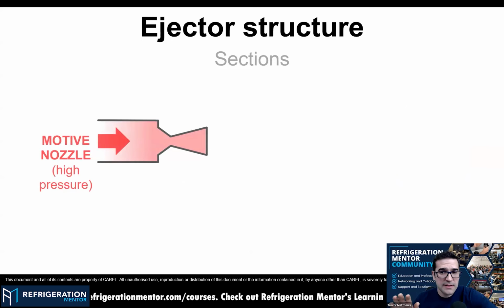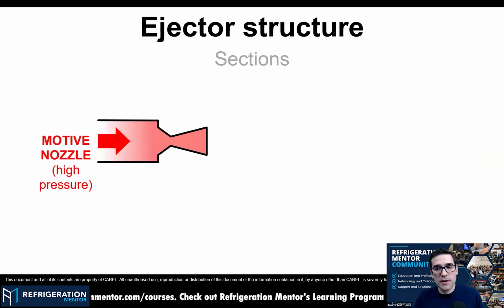Yeah. And this all goes back to design. So if you're a technician out there, this is not what you've got to worry about. The manufacturers that are listening, though, it goes back to design. Do you meet every gap if you're using ejectors with different compressors? Because if you go with too small compressors, maybe you have too big of gaps, or with all the same size compressors, you may have big gaps. So this goes back to the design when you're using ejectors, and they've got sizing software out there. I've seen it, you know what I mean? So if you're a manufacturer, you can go into the sizing and really plug it all in, because you've got to know the ambient, you've got to know the climate. There's a lot to it as a manufacturer, but when it's done right, it works really well.